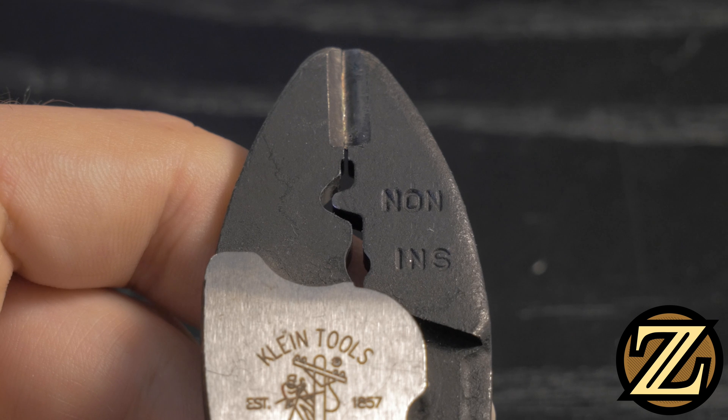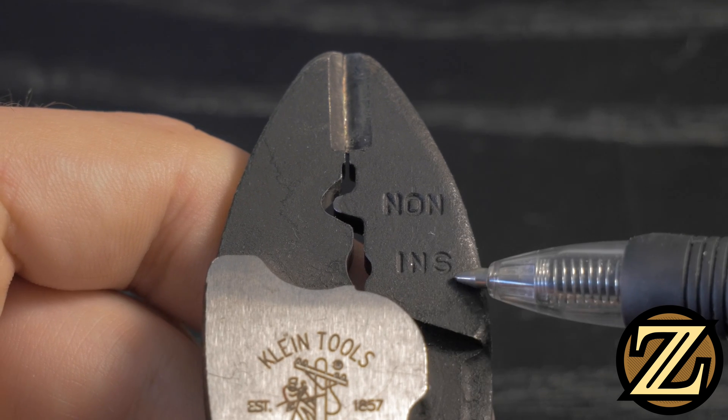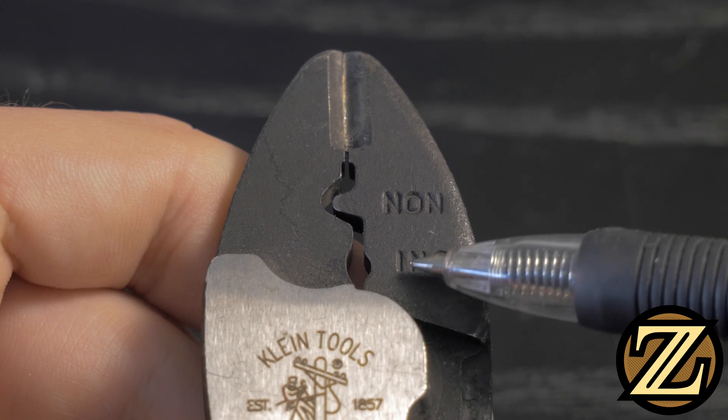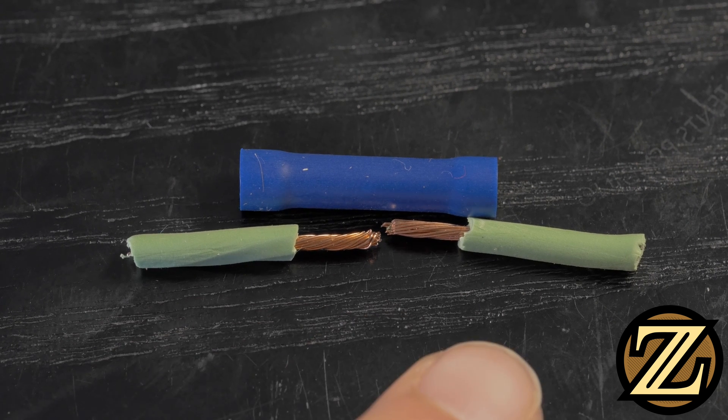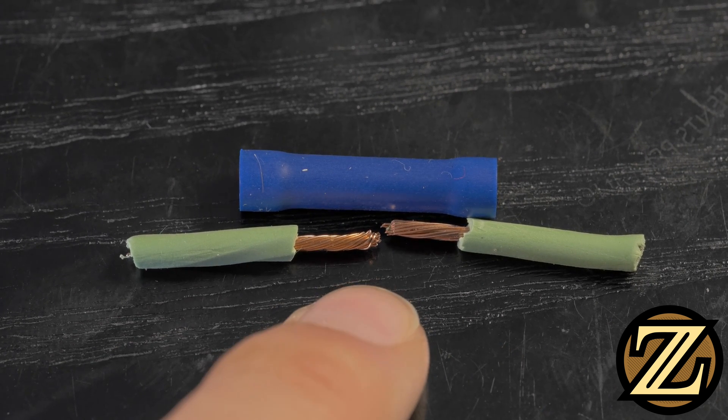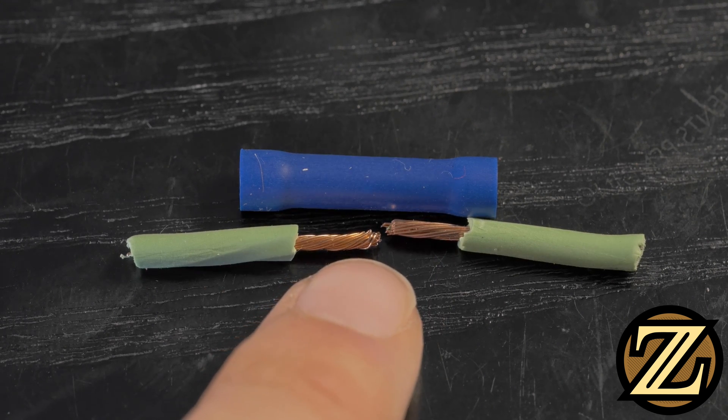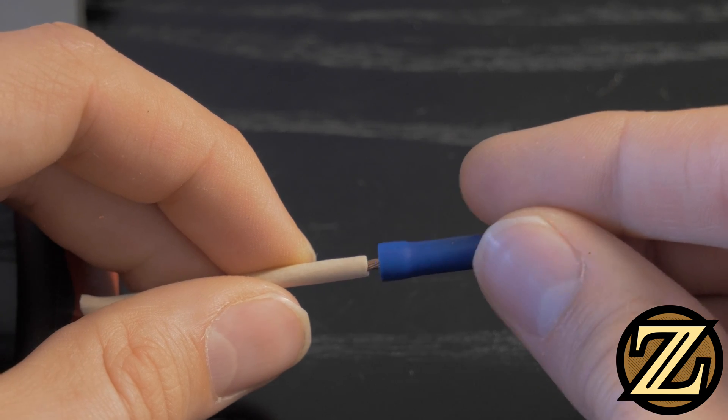Now let's take a look at this crimper here. We see that there are only two slots, one for non-insulated and one for insulated terminals. Since our butt splice is insulated, we'll be using this slot here. Now let's take a look at butt splices. Butt splices join two wires together. When you strip the wires, you want it such that the center of the wire is approximately in the center of the butt splice. Feed one end of the wire into the butt splice and then crimp it.